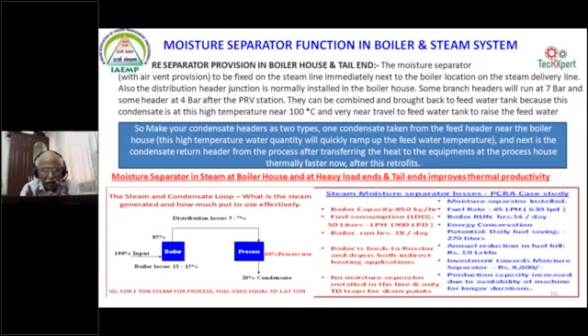Here, it is a jugaad we have suggested during our energy audits, and it has been implemented in many of the textile processing units in Tirupur and in many places in and around this textile region, where they are using these package boilers, which don't have a breathing space for the steam to come out, and then the water has to come out of the system. Once it is removed from the boiler and from the boiler house, let us have the condensate return as one, as the feed and return, and one as the return line from the process.